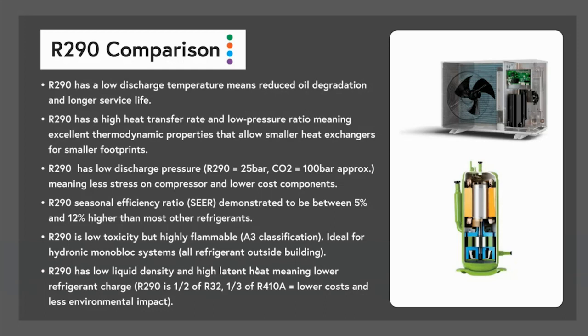R290's seasonal efficiency ratio, the SEER, which is one measurement of efficiency, has been demonstrated in a lot of different studies to be somewhere between 5% and 12% higher than most other refrigerants. So it's really up there in terms of performance amongst all its peers. The other thing about R290 is that it's low in toxicity, but it is highly flammable. So it has an A3 classification. A3 is the highest there is, so it doesn't get any higher than that.